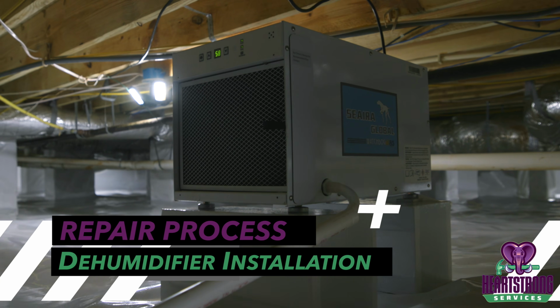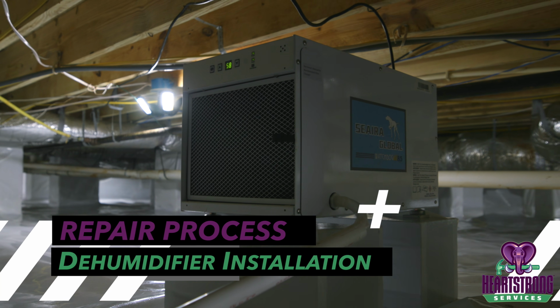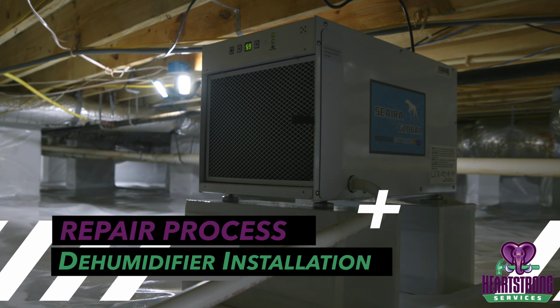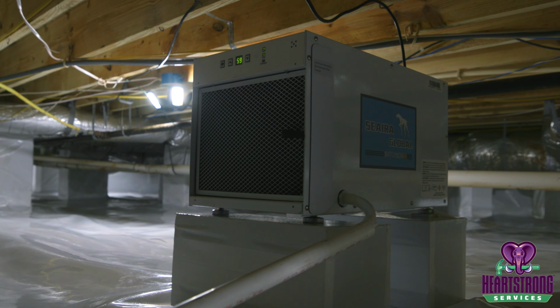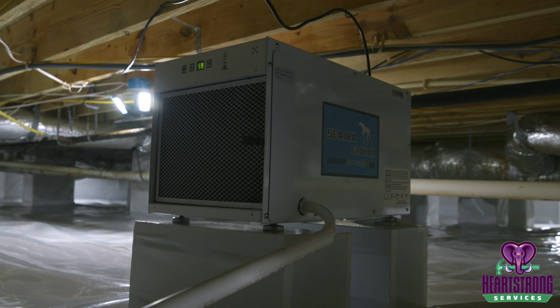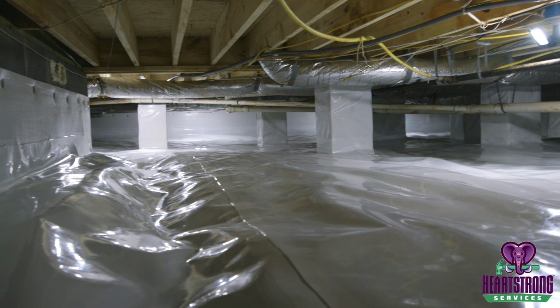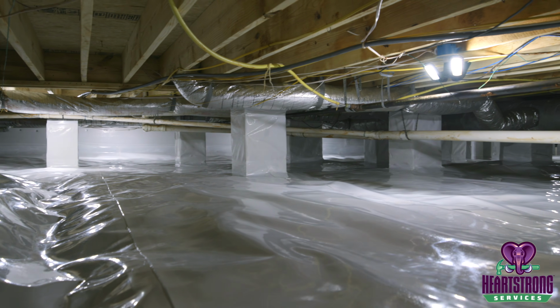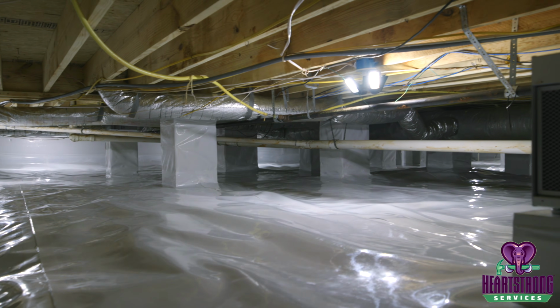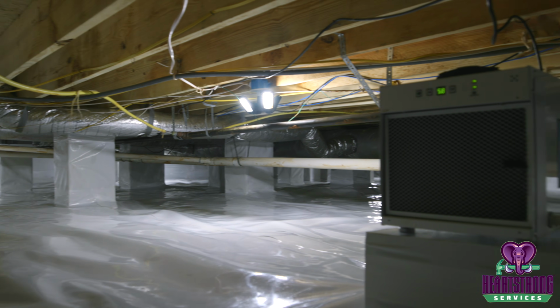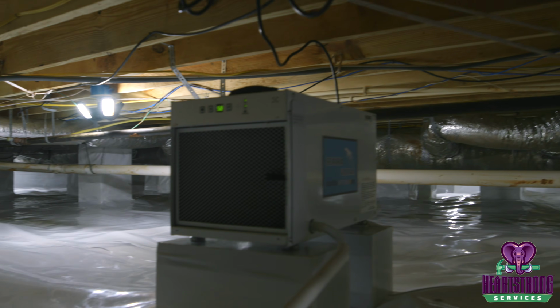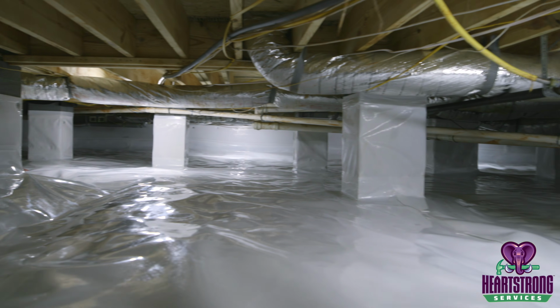To maintain long-term humidity control, we install a dedicated crawl space dehumidifier. The unit is elevated on cinder blocks, which are wrapped in white to blend seamlessly with the liner. Rather than relying on a condensation pump, we use gravity drainage tied directly into the crawl space drainage system. Water exits automatically without moving parts that can fail.